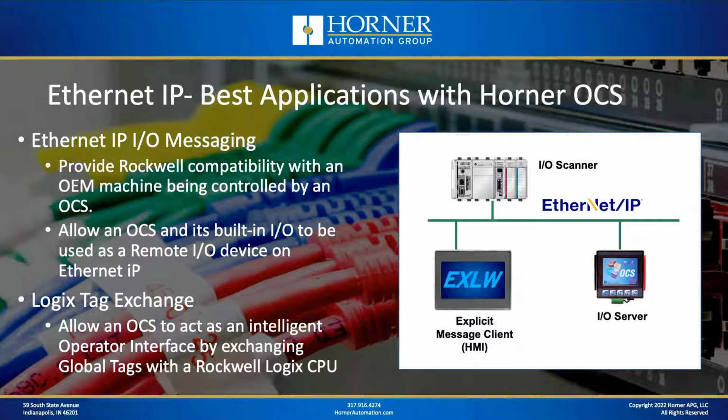And then in the scenario where you might want one of our OCS all-in-one controllers to act like an intelligent operator interface, communicating with, say, a CompactLogix or ControlLogix CPU, you can do that using something called Logix Tag Exchange. That allows an OCS to act as an intelligent user interface because it's not just displaying data on the screen. It also has logic capability and built-in I/O capability and some additional functionality as well.